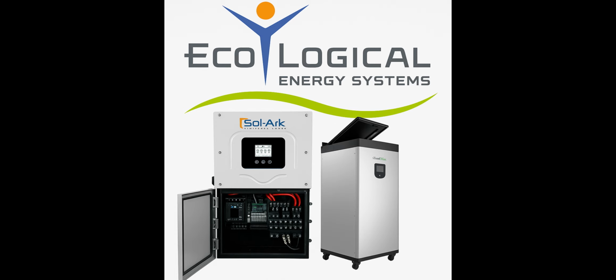Interesting alternative. All right, let's zoom in on the Fortress Power eVault Max itself, the physical side of things, how you actually install it and how it works day to day. We know it has to be connected in parallel. What does that mean for setting it up? Absolutely no connecting them in series, like you might with AA batteries and a flashlight. Right, parallel only. You can connect up to a whopping 20 of these 18.5 kilowatt modules in parallel. 20? Giving you a massive total storage capacity of 370 kilowatt-hours. That's huge. It is. When you're installing multiple units side by side, the manual recommends leaving at least 5 inches of space between each battery for proper ventilation.